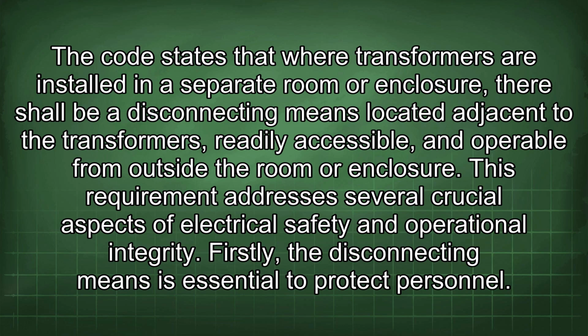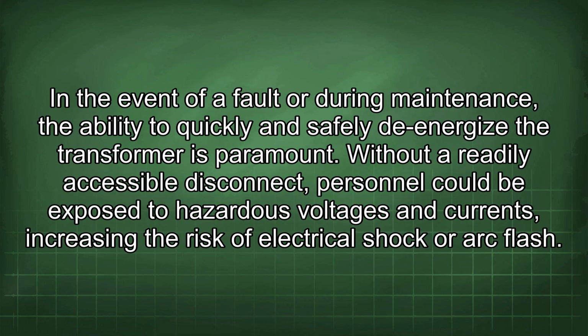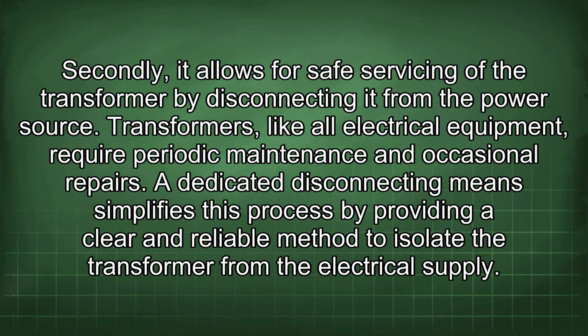This requirement addresses several crucial aspects of electrical safety and operational integrity. Firstly, the disconnecting means is essential to protect personnel. In the event of a fault or during maintenance, the ability to quickly and safely de-energize the transformer is paramount. Without a readily accessible disconnect, personnel could be exposed to hazardous voltages and currents, increasing the risk of electrical shock or arc flash. Secondly, it allows for safe servicing of the transformer by disconnecting it from the power source.